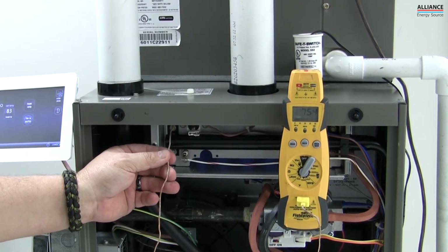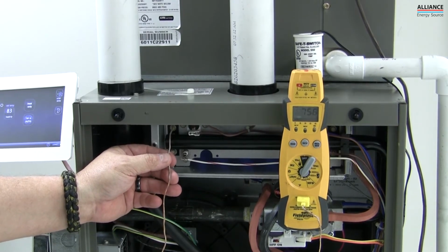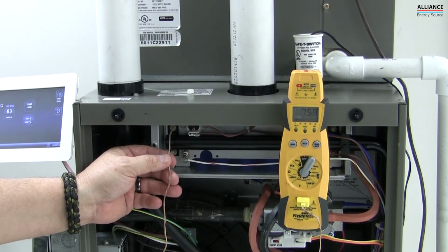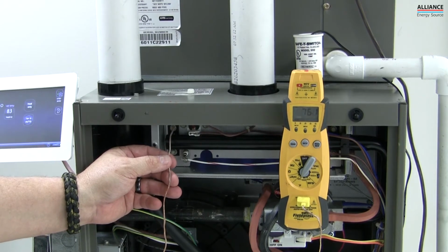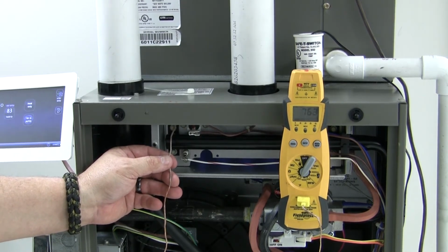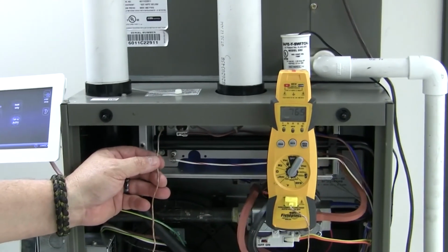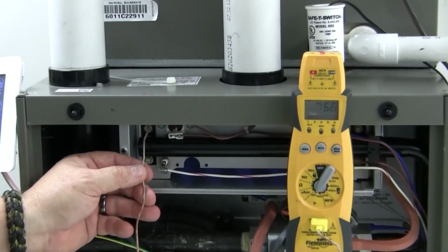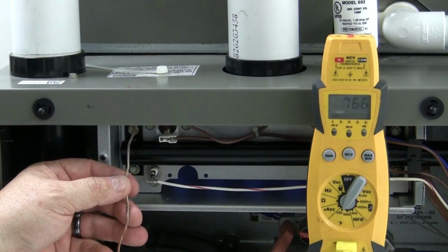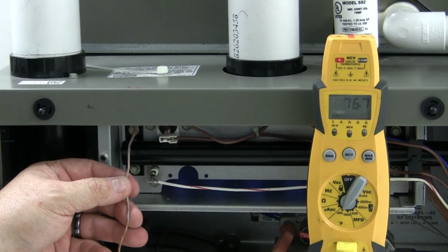If you notice it start to climb dramatically, that is a good indication that you have a restricted airflow or restricted vent or something along those lines. It could also be high gas pressure. So then you would want to check into it deeper, check gas pressure, and make sure you have nothing obstructing your vents.